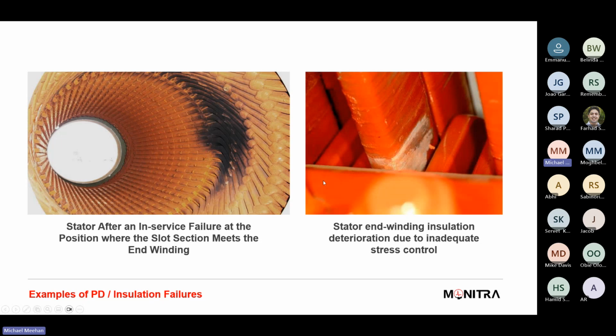So it's definitely worth, if you are in a position where you're looking to buy critical HV machines, it's worth understanding how the machine is constructed, how it's actually made, and then when you're thinking of buying, it's like anything. Sometimes if you buy something that's a bit cheaper, it could be because the reliability of it might not be so good, but you need to know what things to look at. So it's certainly an area to consider when you're looking at your machines in terms of future purchase or ongoing maintenance for sure. Visual inspections around the end winding, if you do have the opportunity while the machine's off, is very good. So yeah, certainly do that.